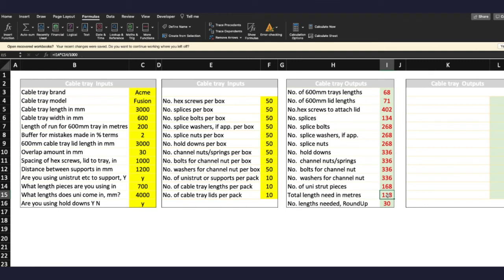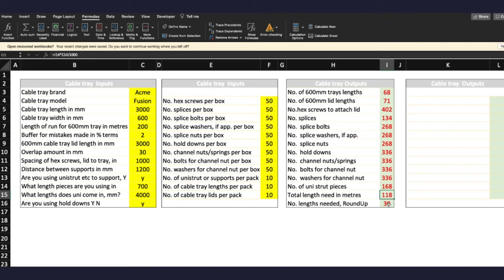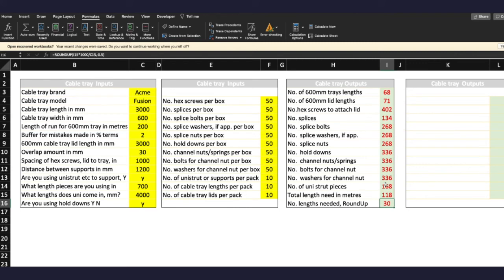Now the total length of Unistrut needed in meters, and that gives you 118 meters. So effectively we've got 168 pieces at 700 millimeters each and this makes up 118. And then of course the number of lengths required. Now this doesn't assume that you've got spare bits of Unistrut. If you have, fine, that's great, use them. But this references again I15 which is the total length, right, multiplied by 1000 because we're doing a millimeter to meter conversion, and then we divide by C15, what length does it come in, and then we round up to 30.